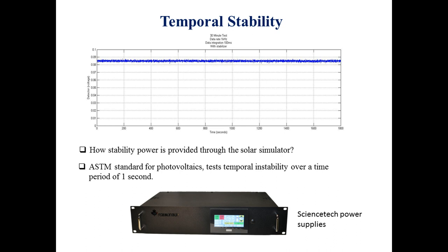Next, we come to another important characteristic, which is temporal stability. The sun, as a consistent source of power, has an irradiation that is very stable. Temporal instability tests how stable the output power is of a solar simulator. If there are drastic fluctuations in the irradiation of the solar simulator for a given amount of time, it is not very stable. To standardize this property, standards such as ASTM for photovoltaics regulate the test duration for temporal instability. In this way, the consistency of the output power is classified by class A, B, and C as well.